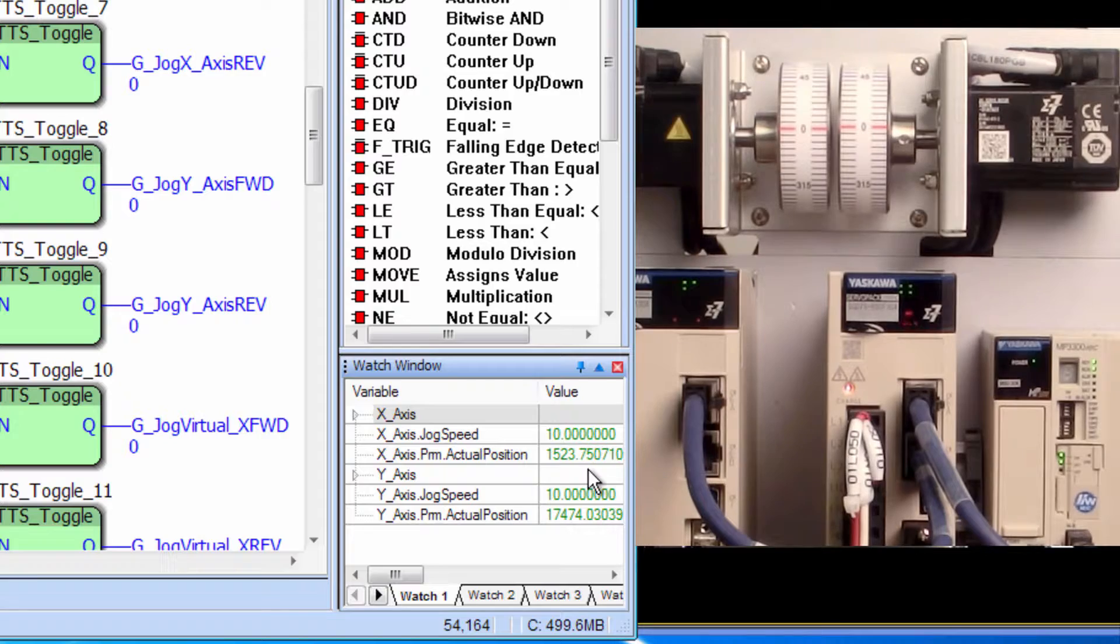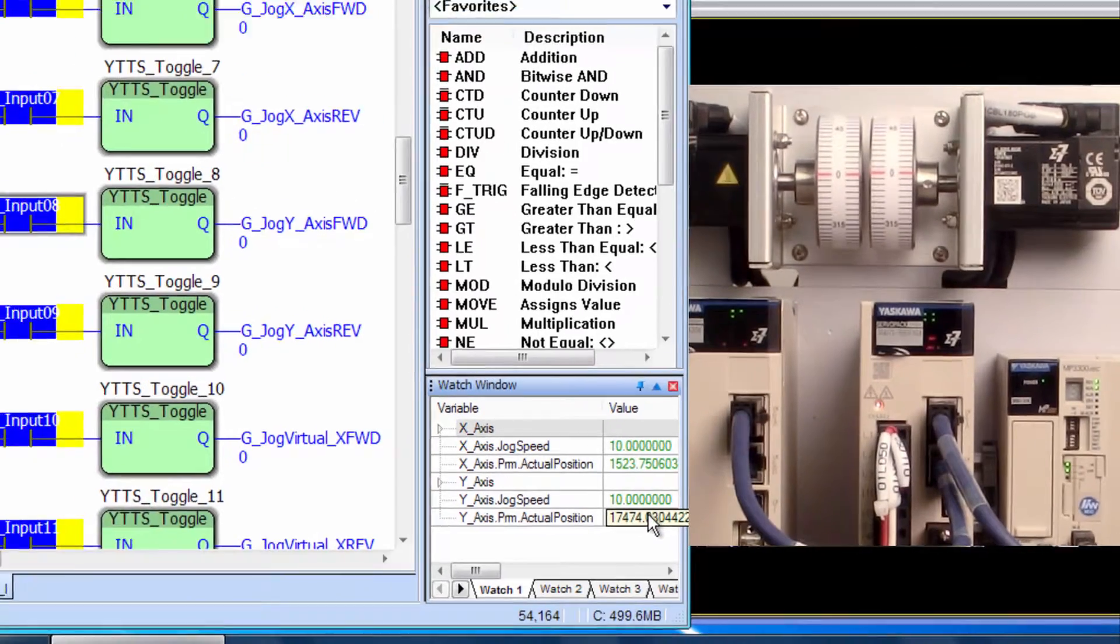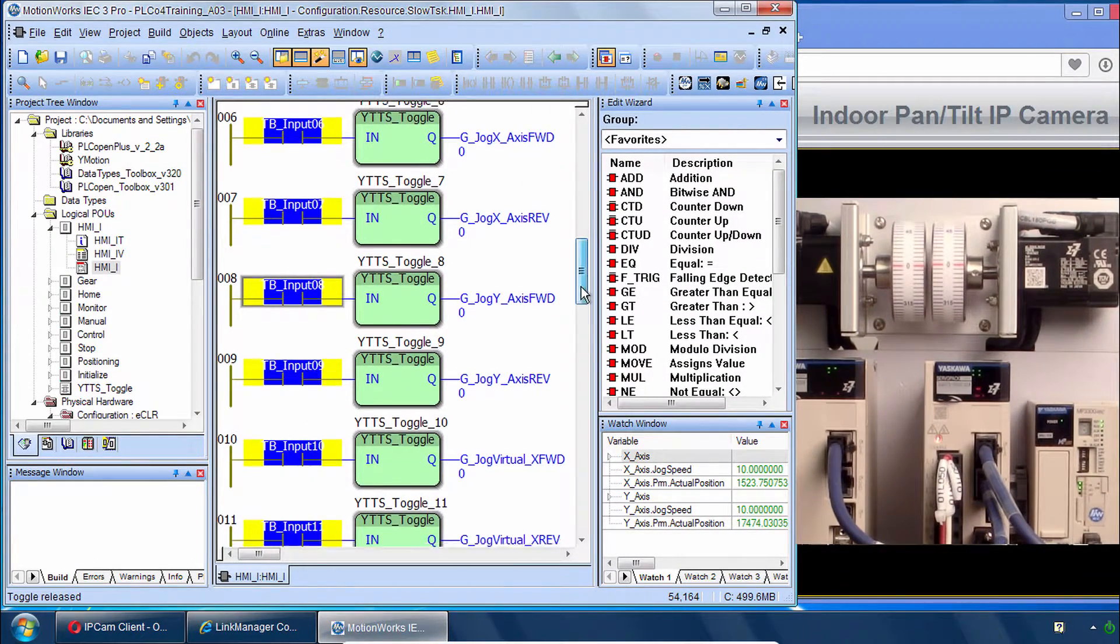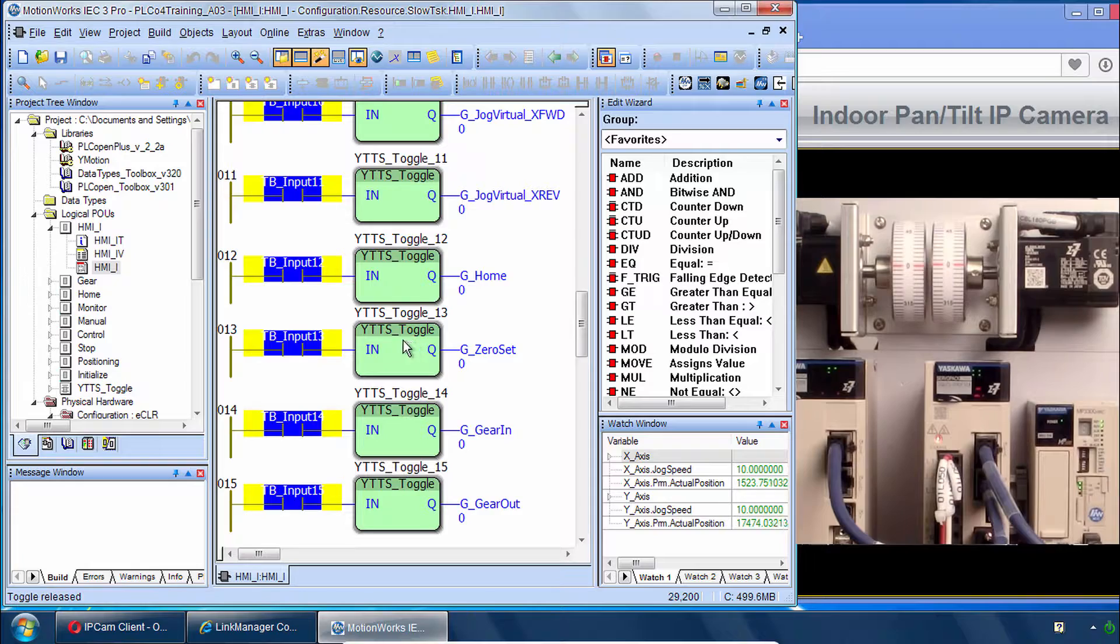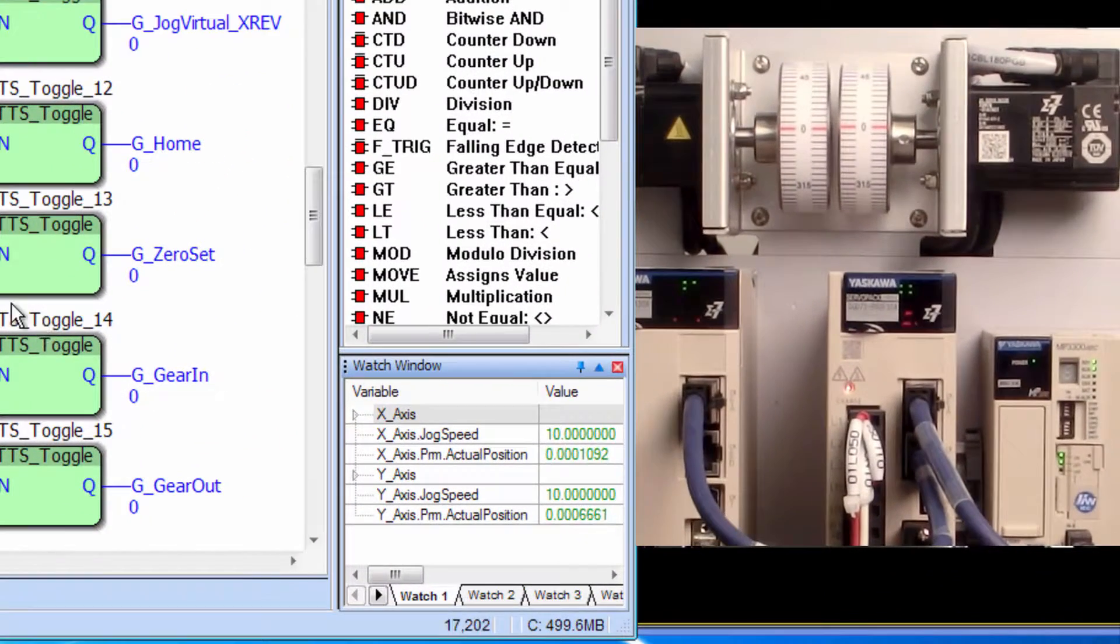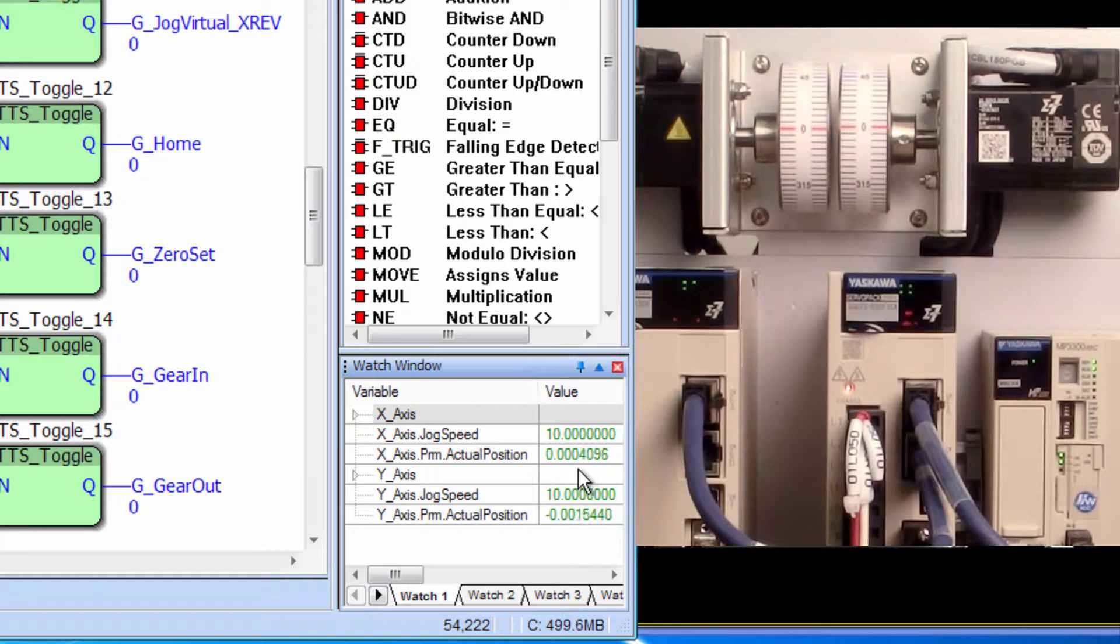Down in the Watch Tab you can see the actual position. And although the Servos are at position zero the feedback position is not at zero. So scroll down to Rung 13. And we'll click to set the zero point. And now the actual positions are zero.